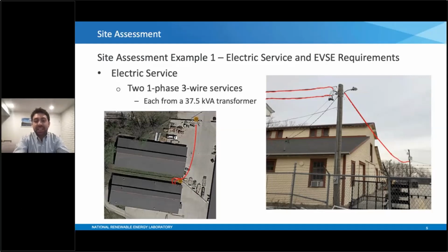The first step is highlighting the lines where utility services come in. Here we've highlighted in red the different service drops from the transformer visible in the distance in that right photo. We notice there are two different service drops going to the building, the lower of the two in the picture on the left. So we can deduce there will likely be two service panels inside. We also noticed a 37.5 kVA transformer cluster mount with three transformers, all rated at 37.5 kVA - something we can discuss with the utility companies if it comes up later.